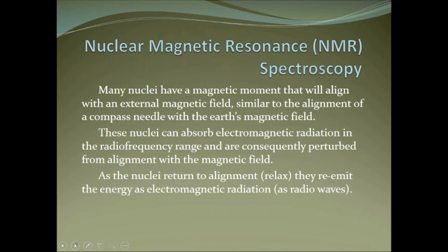The basic principle behind nuclear magnetic resonance spectroscopy is that nuclei can behave like a small magnet, and so if we put them in a magnetic field, like a compass needle, they will align with the field. We can push them away from alignment using radio waves, and when they return to alignment, they give off energy in the form of radio waves, which we can measure.